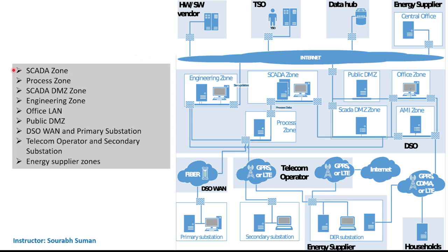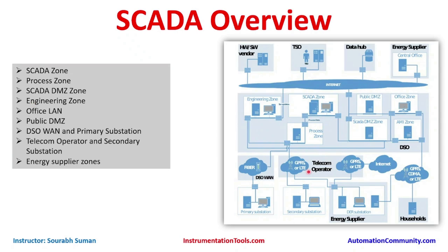DSO stands for Distribution System Operator. The DSO zone can be a dedicated channel managed by the distribution system operator or connected via fiber communication. There is also a telecom operator zone for secondary substations connected by telecom communication. Additionally, the AMI zone handles collector readings of energy data from households, industrial customers, and allows office staff to query meter status and issue switching commands to specific customers — particularly when smart meters are used.